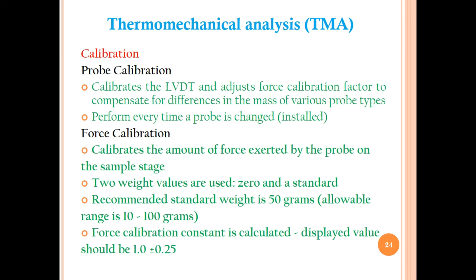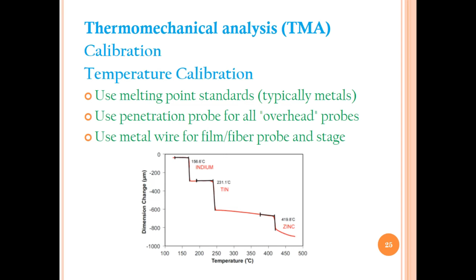Now we look into another calibration factor, that is the temperature calibration factor. In the temperature calibration, using melting point standards, typical metals will be used for the temperature calibration of the TMA instrument. Use a penetration probe for all overhead probes. Use metal wire for film fiber probe and stage. In the diagram you can see indium metal, tin metal and zinc metal used for different temperature calibrations. Indium is 156.6 degrees, tin 231.1 degrees, and zinc 419.8 degrees centigrade. These metals are used for the temperature calibration of TMA instruments.